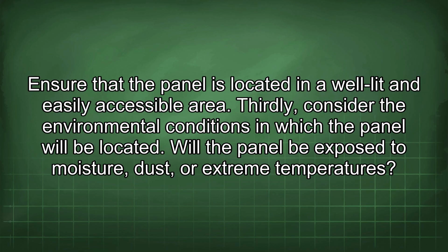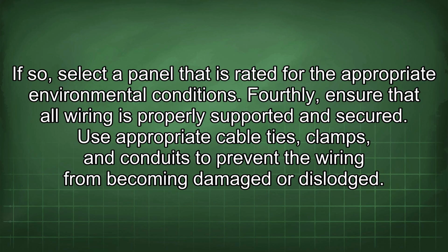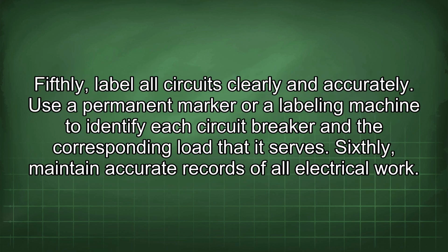Thirdly, consider the environmental conditions in which the panel will be located. Will the panel be exposed to moisture, dust, or extreme temperatures? If so, select a panel that is rated for the appropriate environmental conditions. Fourthly, ensure that all wiring is properly supported and secured. Use appropriate cable ties, clamps, and conduits to prevent the wiring from becoming damaged or dislodged. Fifthly, label all circuits clearly and accurately. Use a permanent marker or labeling machine to identify each circuit breaker and the corresponding load that it serves.